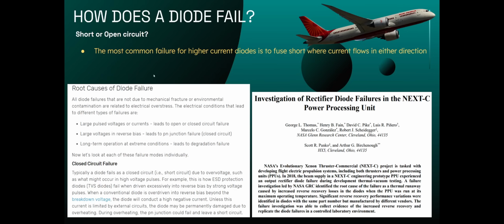So how does a diode fail? The most common failure for a higher current diode, provided it wasn't exposed to ridiculous current, is a fused short circuit. If it was massive current blowing it up, it would explode and open. This is not massive high current — this is transients, just a relatively high current diode which failed.